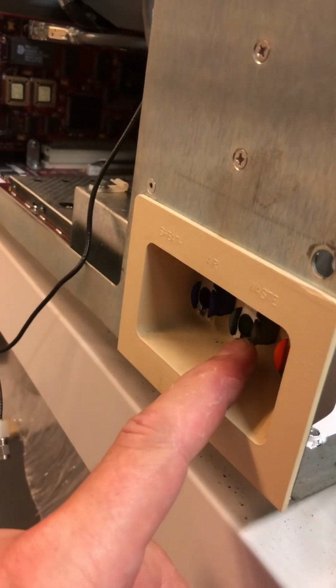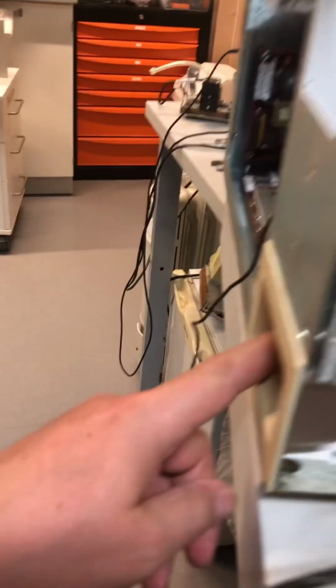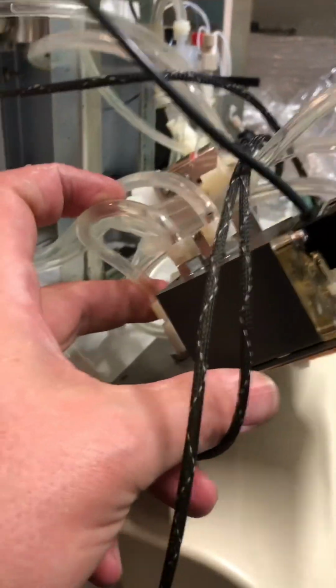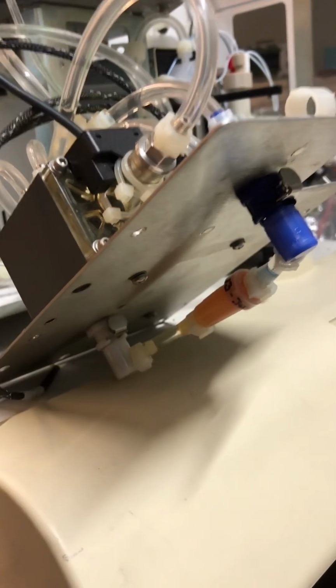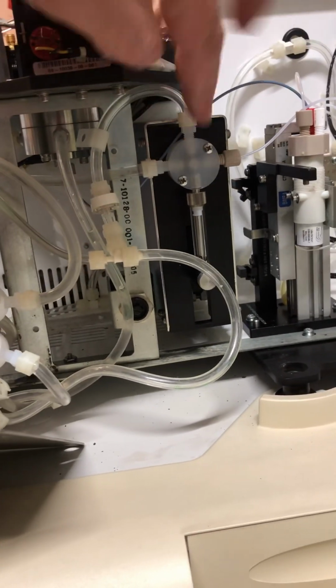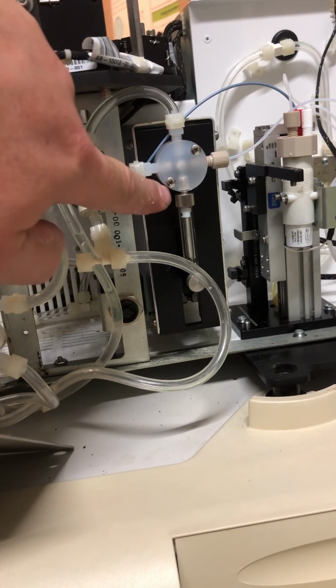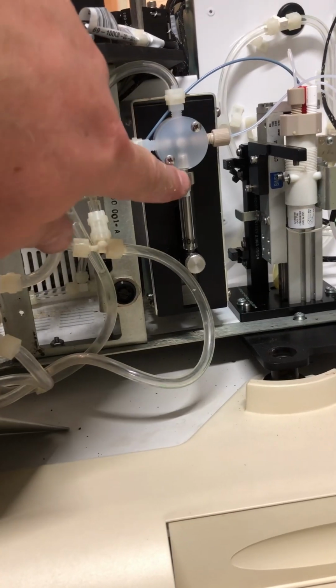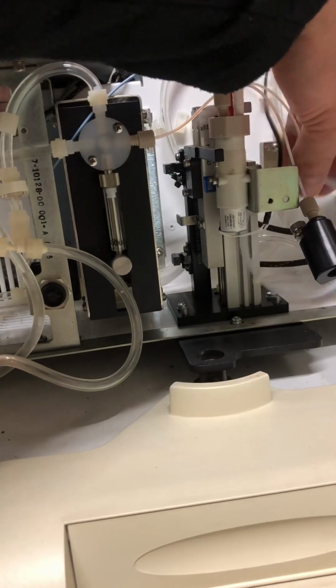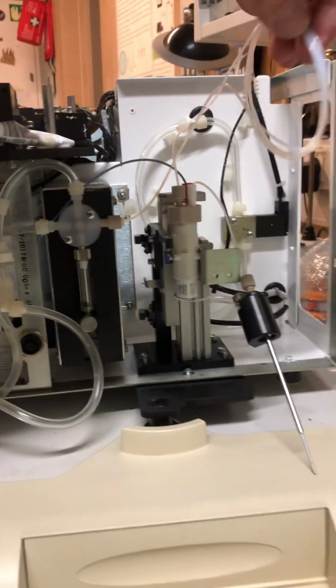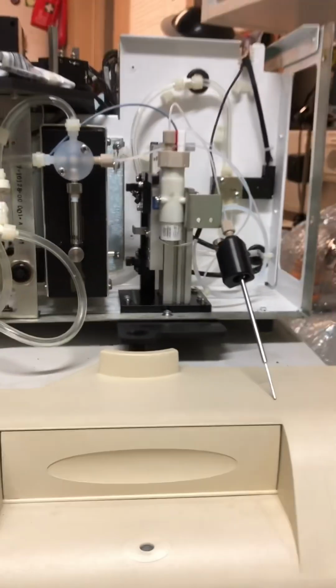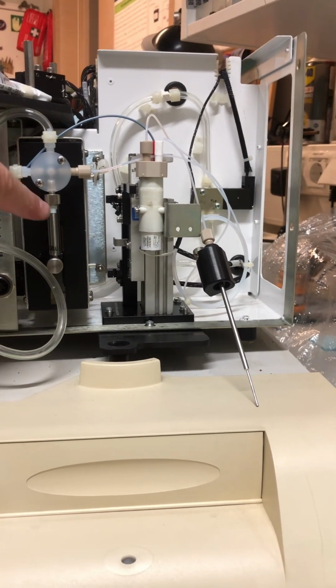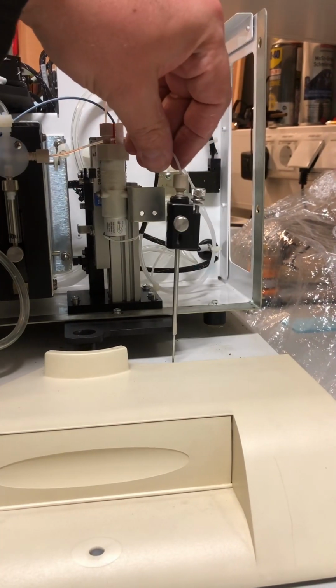Here it goes to the liquid module, and from the liquid module liquid comes in. Here is the pressure sensor. Then this liquid goes through such a box, which is probably a bubble remover, and it also goes through such a thing which looks like a filter, and afterwards it goes to this splitter module.